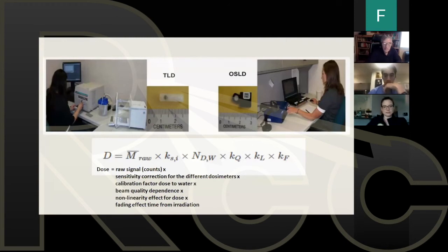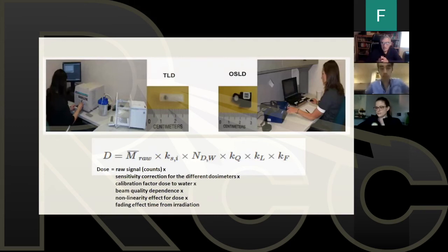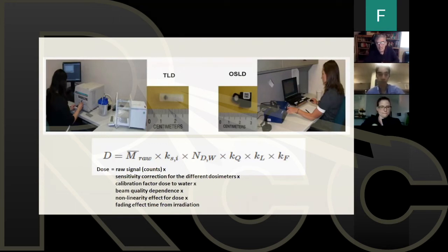Also, with these dosimeters, there is a small nonlinearity. The amount of light given off at 100 centigrays may not be exactly proportional to the amount of light given off at 300 centigrays. So there is a non-linearity to the amount of light given off by dose. So they correct for that. They have figured out all the correction factors to put in. This system is well developed.